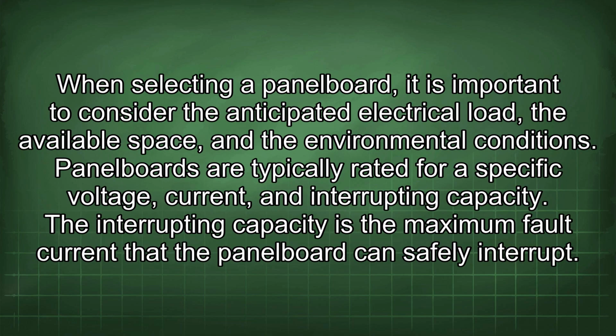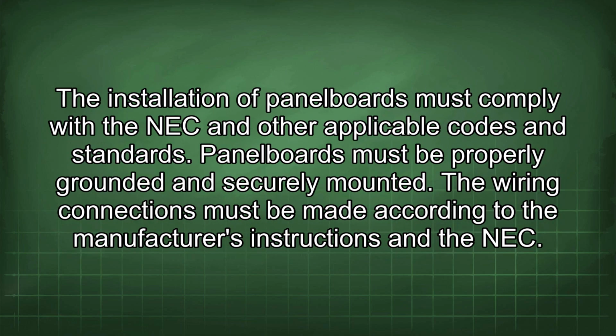When selecting a panel board, it is important to consider the anticipated electrical load, the available space, and the environmental conditions. Panel boards are typically rated for a specific voltage, current, and interrupting capacity. The interrupting capacity is the maximum fault current that the panel board can safely interrupt. The installation of panel boards must comply with the NEC and other applicable codes and standards. Panel boards must be properly grounded and securely mounted. The wiring connections must be made according to the manufacturer's instructions and the NEC.